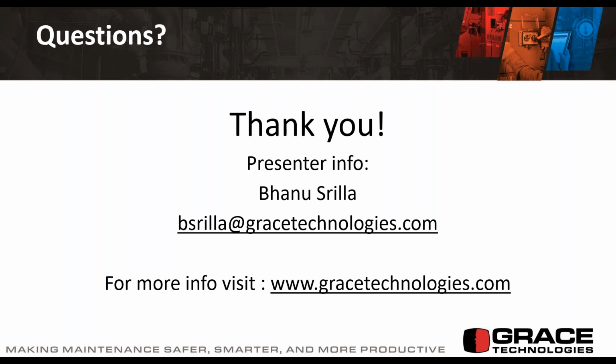Do you use sensors in predictive maintenance, preventive maintenance? So predictive maintenance absolutely uses some type of a sensor-based technology for you to connect it permanently to the equipment, and then from there it automatically sends the data to your systems. So in that way, you don't need to go and perform route-based inspections, or you can reduce your route-based inspections because you're constantly monitoring it on a remote basis.